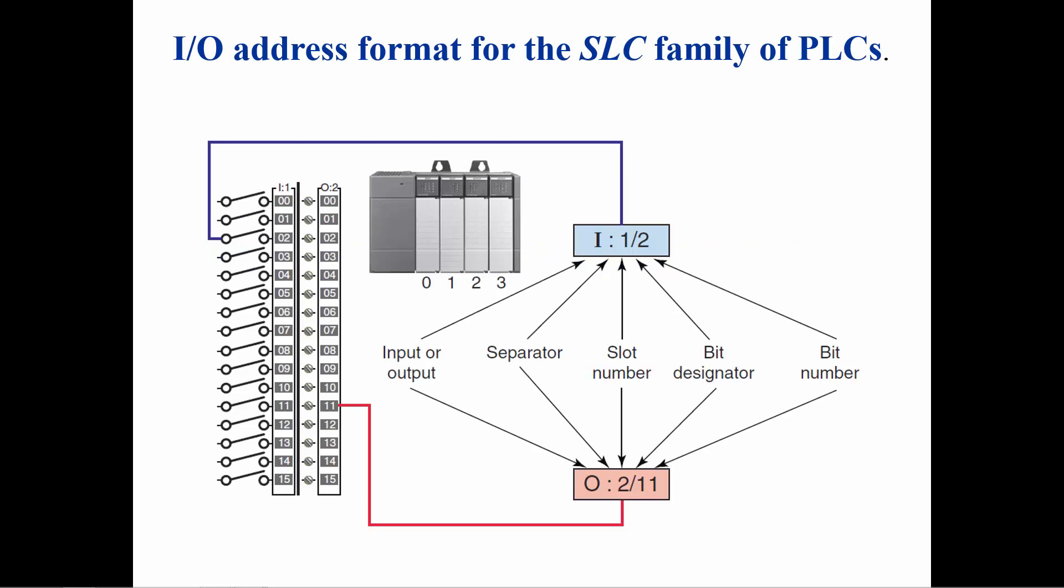The format for addressing with the SLC family of PLCs consists of letters, numbers and symbols that identify the physical location of the input or output modules. An input will have an I for the first symbol and an output will have an O followed by a colon.